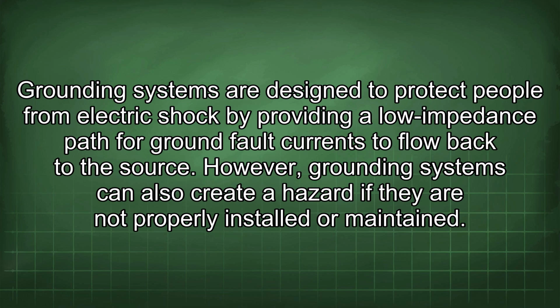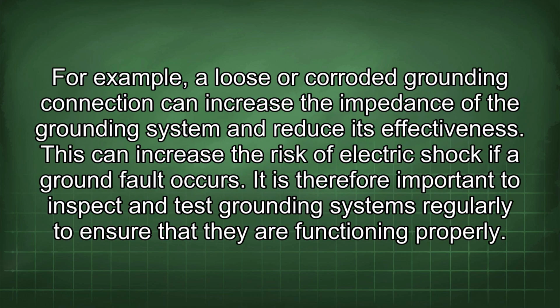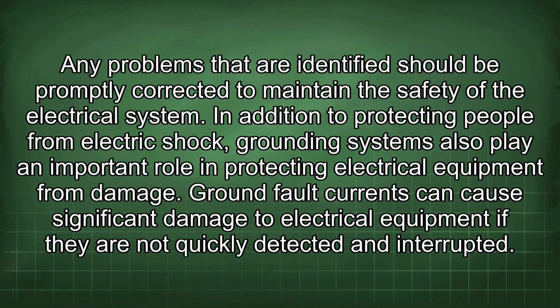However, grounding systems can also create a hazard if they are not properly installed or maintained. For example, a loose or corroded grounding connection can increase the impedance of the grounding system and reduce its effectiveness. This can increase the risk of electric shock if a ground fault occurs. It is therefore important to inspect and test grounding systems regularly to ensure that they are functioning properly. Any problems that are identified should be promptly corrected to maintain the safety of the electrical system.